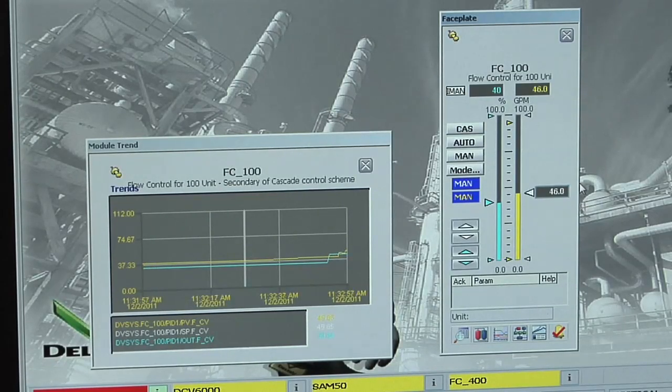So the process went up, and one change you'll see now is that the set point is tracking the process value, which is one of the settings that we had made. So that does also confirm for us that all the settings got into this block. So now we're actually running on control within the device. And no big jumps, no big anything happening here, just nice smooth transition from one method to the other.